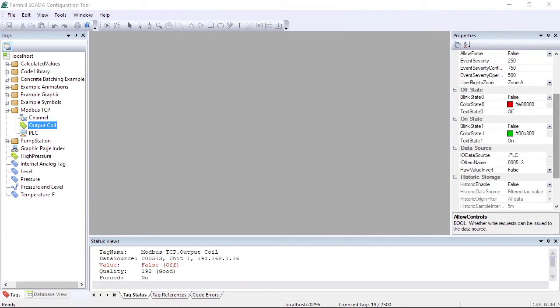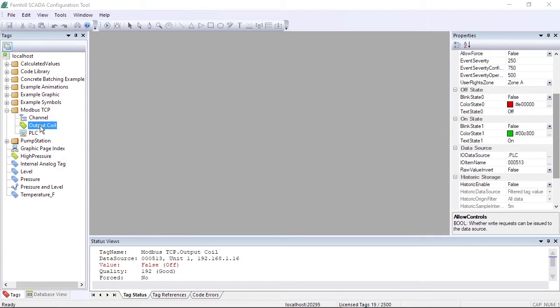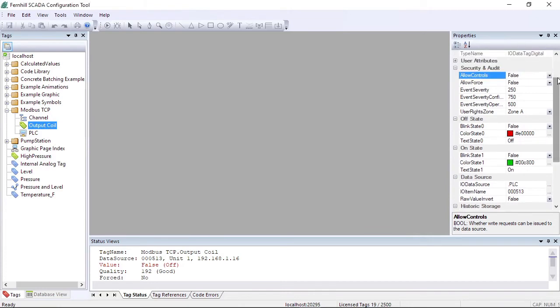Fernhill SCADA has a secure by default policy, so write operations to real hardware have to be explicitly enabled. To do this, make sure the tag you want to change is selected in the tag window. Then in the properties window, set allow controls to true.